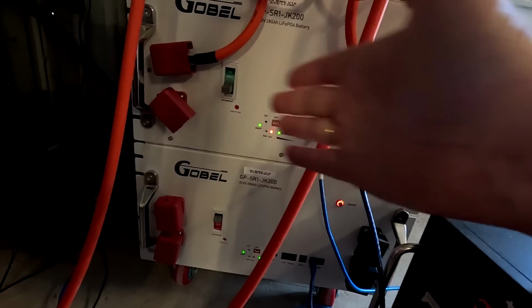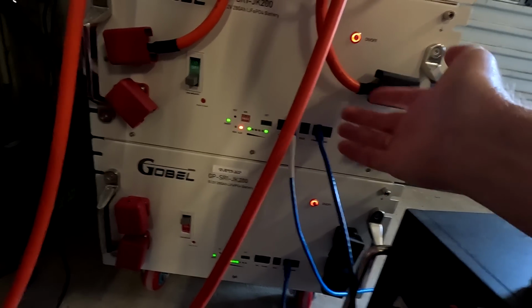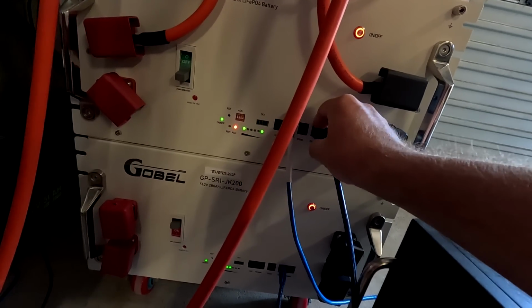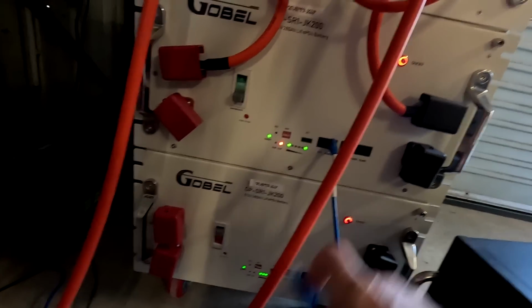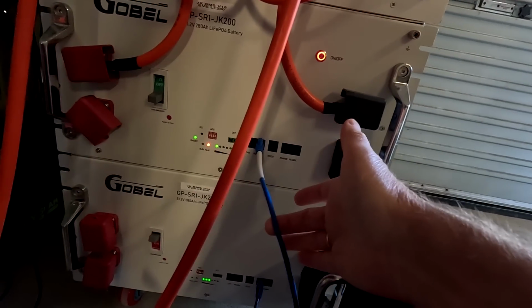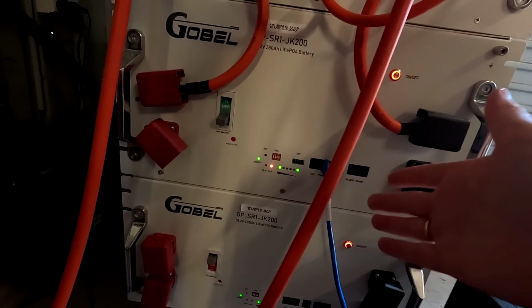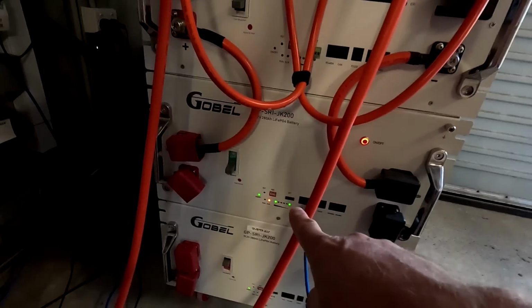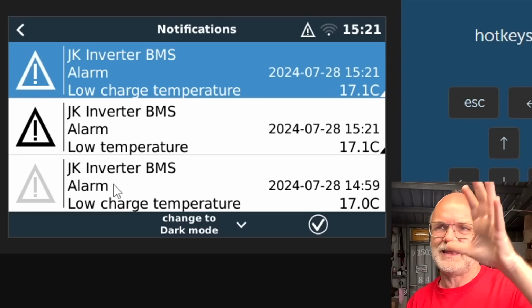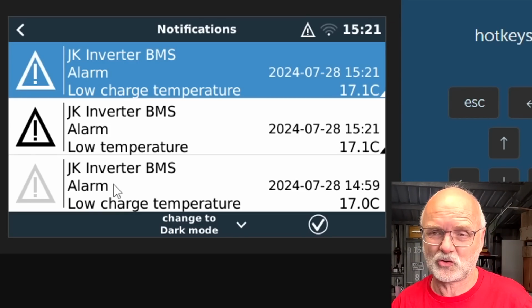What happens if we have only one battery? Yeah. So to demonstrate this, I just disconnect the communication cable to the slave and we have only the master connected to our Victron system, to the inverter. We still got the alarm running. And there you can hear it. The Cerbo GX, which is connected via CAN to this BMS, has an alarm. We can see here's an alarm coming up in the Victron remote console.